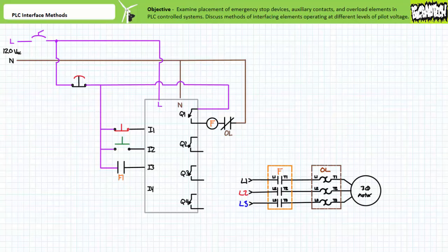F contactor coil, and both the primary and auxiliary F1 contacts return to their deactivated states without the involvement of the PLC. However, by virtue of the F1 auxiliary contact, the PLC is made aware that the F contactor is open because of an overload and can initiate any special actions specific to the process under its direction. Other feedback methods for motor starters exist. However, this, in my personal opinion, is the one that delivers the most bang for the buck.